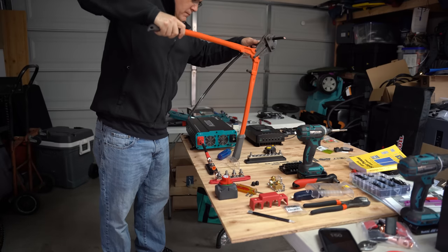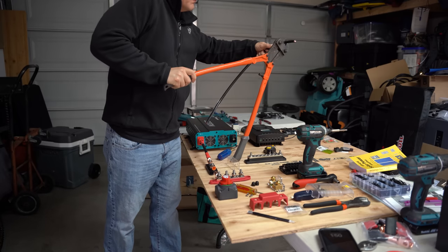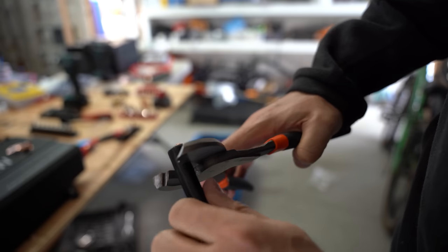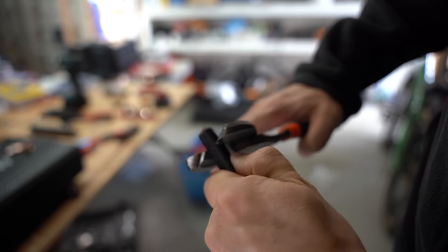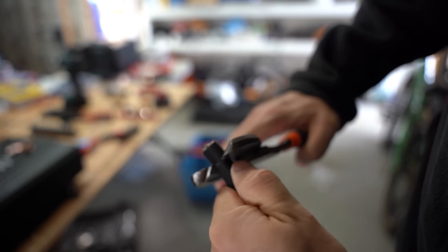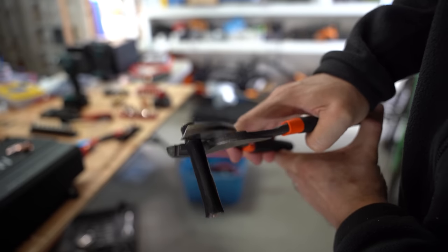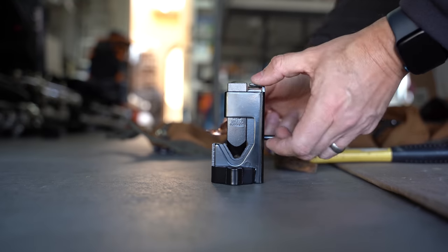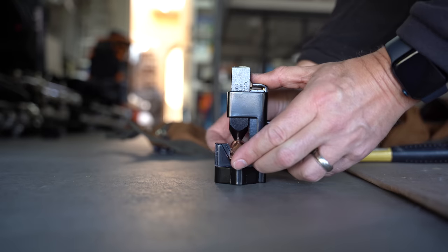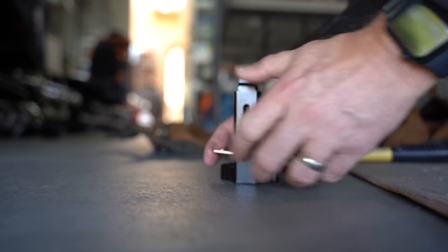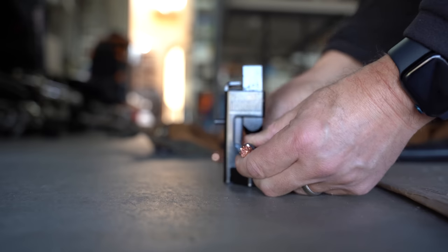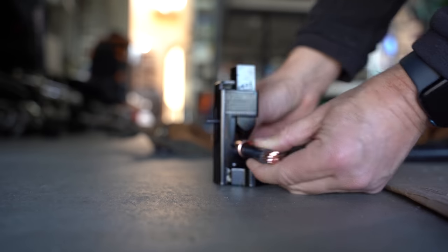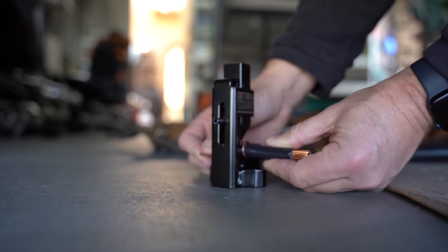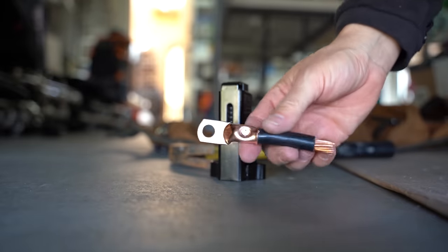Due to the thickness of this particular cable, I had to use a bolt cutter to cut the wire. Now, once I cut the wire, I had to strip off the insulation off both ends of the cable. I used this cutting tool and was very careful to gently make cuts to get through the insulation and not impact the metal inside the wiring. I had to then add the cable lugs on the end. As shown, I had to use a special tool to hammer the cable lugs to the wire. There are tools that are smaller to connect the lugs to cables. We're going to cover those shortly, but due to the thickness of this particular wire, I had to use this particular device, which requires you to hammer it down.